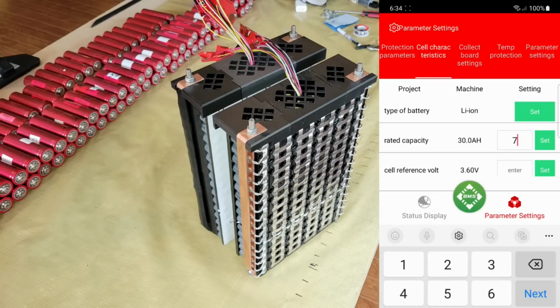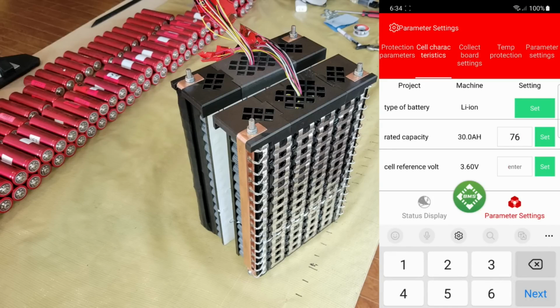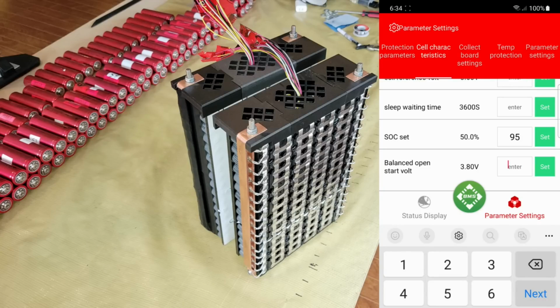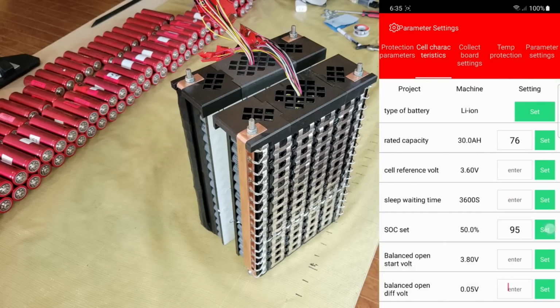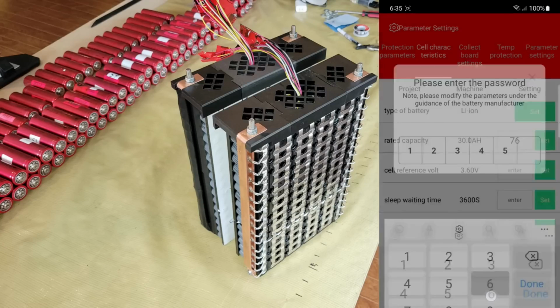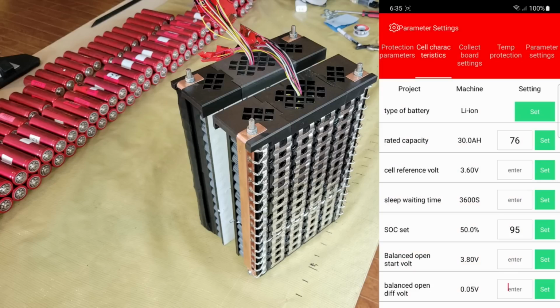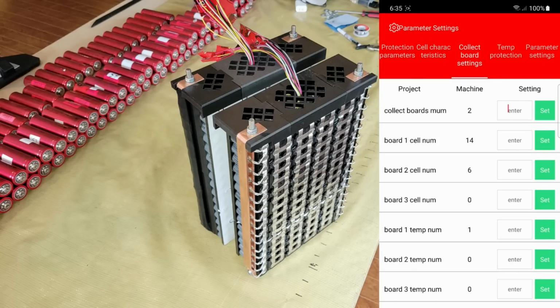You can also change the state of charge meter here, which I'll do now to show you how, but it's best to do this after the battery's been cycled a few times, then charged and left to rest for 24 hours. After that, set the meter to 100% in the app, and it should keep track of how many kilowatt hours you use or put back into the battery, and compare that with the amp hour rating that you entered to match the state of charge meter accordingly. In order to save any settings that you change here, you need to click the Set button and enter a passcode. The default factory code is 123456.